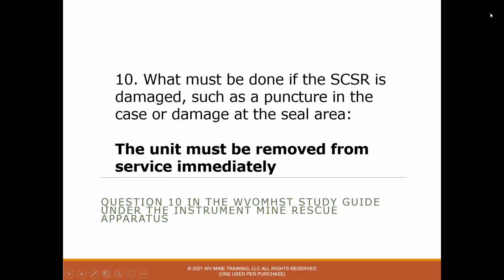Question 10: what must be done if the SCSR is damaged, such as a puncture in the case or damage at the seal area? The unit must be removed from service immediately. So if it's damaged or the seal's broken, you just have to remove it from service.